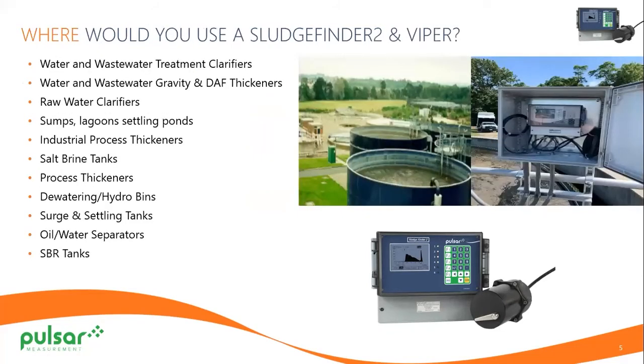Where would you use a Sludge Finder 2 and Viper? Well, there's many places to use the Sludge Finder 2 and Viper. These are some of the common applications. The most common is in wastewater on clarifiers. If you have an application where you think a Sludge Finder 2 with Viper would work, my thing is let's trial it. Let's set up a trial. Let's get the sensor in. Let's make sure that we're seeing that settlement in the application, whether it be salt brine tanks, oil and water separators, SBRs, all about trialing it. If you don't trial it, you're not going to know.